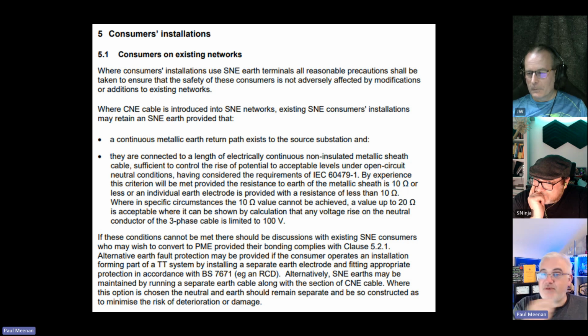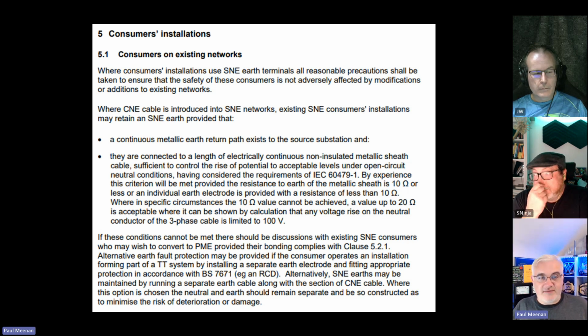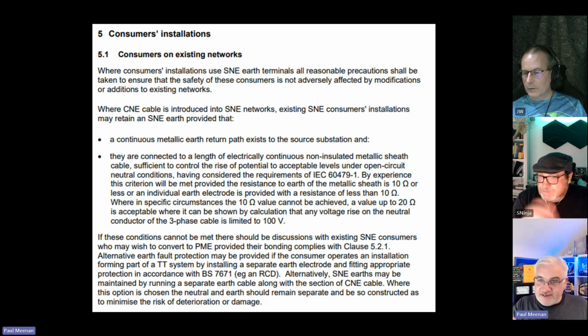All right then, how the bleep do you explain diverted neutrals? It's great that you're trying to comply with ESQCR, but you're not, in reality. Sorry, you're just not. Where CNE, combined neutral and earth, is introduced to SNE - aka, in our opinion, the lazy man's answer - existing separate neutral and earth consumer installations, aka when you look at a TNS head, may retain an SNE earth provided that - so you can adapt it, PME outside and leave it TNS inside - as long as a continuous metallic earth return path exists to the source substation.